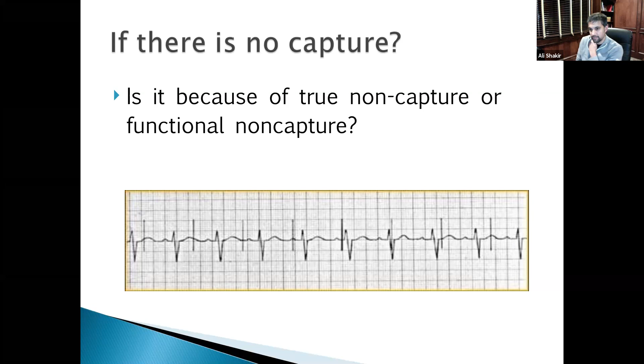So for example, if you look at the third spike, like you said, it's after the T wave, from there you should probably capture the ventricle. Even the fourth spike, right on top of the P wave, the ventricle should at least capture there. So in this case, you have episodes where some spikes are true non-capture. On the other hand, if you look at the fifth spike, right on top of the QRS, or the sixth one, you can see that there's no way the ventricle is going to be ready. So in that case, you have functional non-capture as well. Okay, so in this slide, you have both true non-capture and functional non-capture. It just depends on the timing of when the pacer spike's delivered to figure out which of those two it is. Does that make sense? Yeah, absolutely.